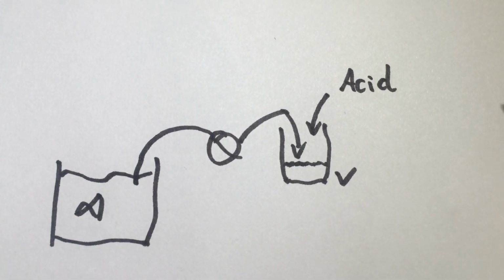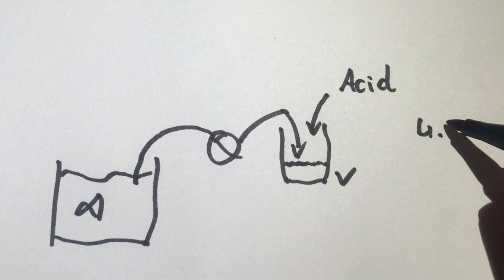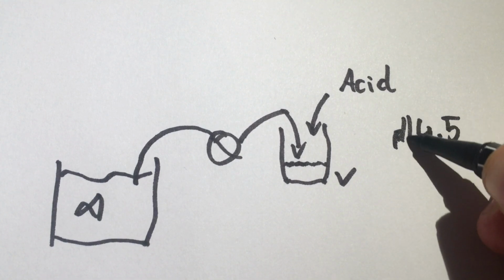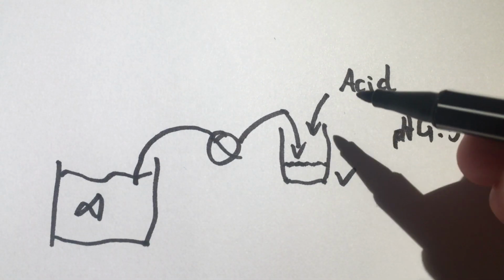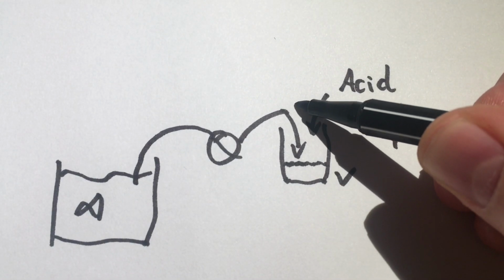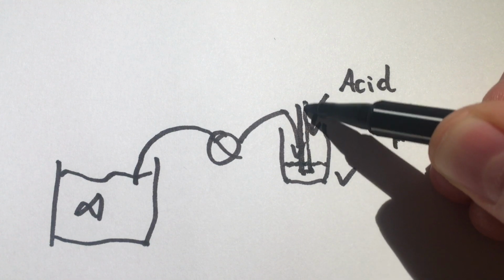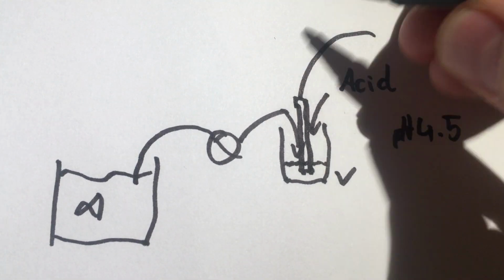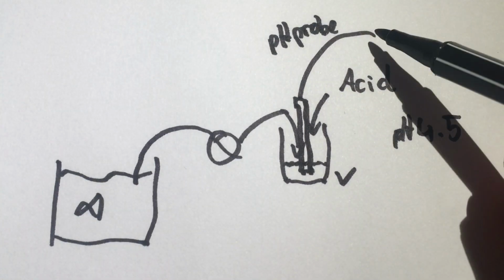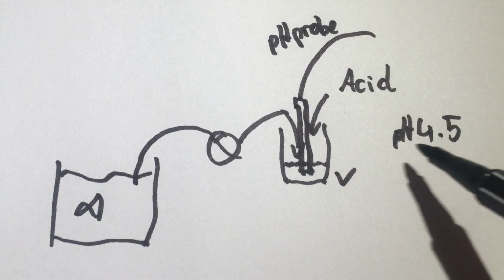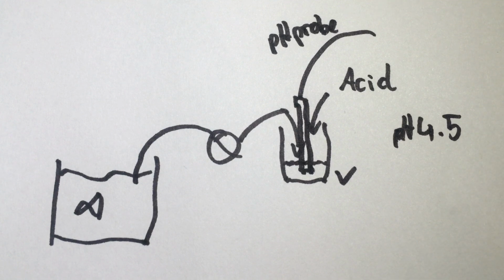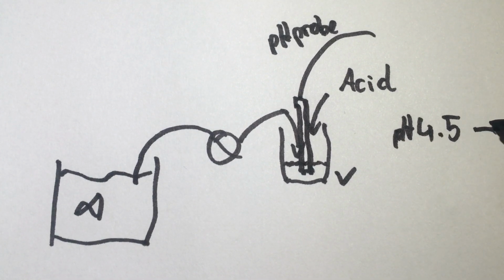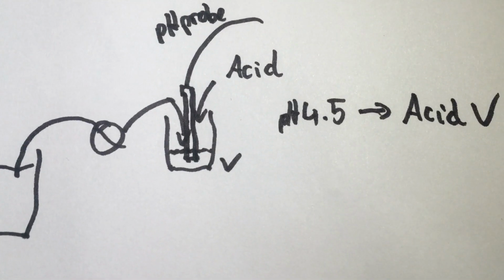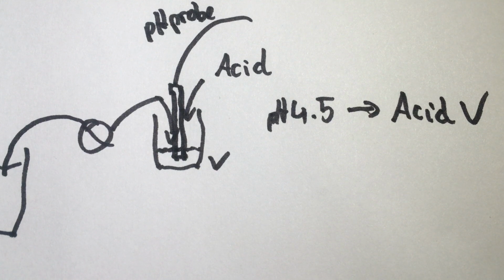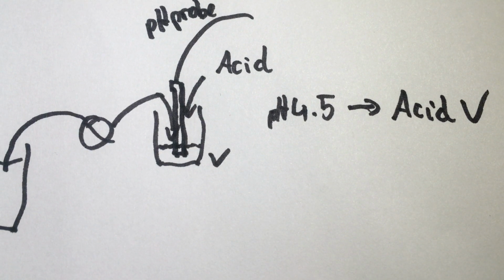And to know when we reach this threshold of 4.5 pH, we have a pH probe in there that measures the pH, and once this threshold is crossed, it stops, and then we have a volume of acid that was required. And with this we can then calculate alkalinity, and we can do this with the following formula.